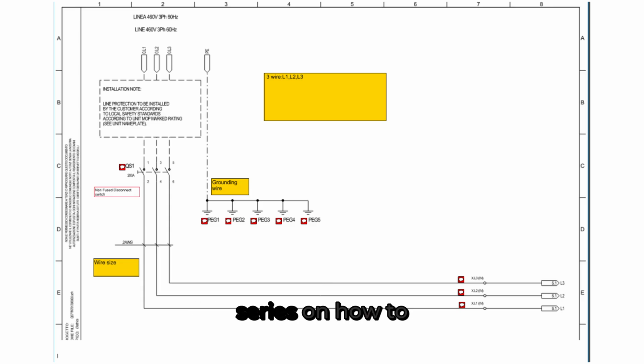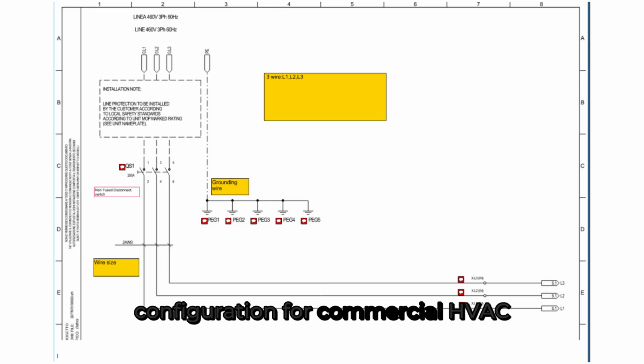Welcome to this training series on how to read a wiring diagram of an air-to-water heat pump. We read the wiring diagram from left to right and from top to bottom. At the top, we see the power specification for the heat pump. This tells us that the unit operates on a three-phase 460-volt electrical supply, which is the most common power configuration for commercial HVAC equipment in North America.